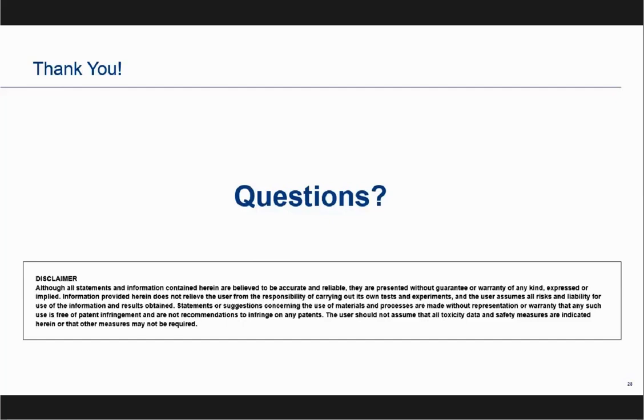Good, good. Okay. Got a question about the unloader solenoid valves. Somebody was doing some math in their head and wanted to know about the expected life of that unloader solenoid. Obviously, it could have millions of cycles a year. I will say that Emerson developed the Copeland brand digital compressors about 20 years ago, and developed a special unloader solenoid valve and coil to go along with those. So we do want you to use the unloader solenoid and coil that come with the unit. It's a very high life unit. It's guaranteed for the life of the compressor. I don't know exactly how many millions of cycles that is, but it is a special coil and it is for the life of the unit.